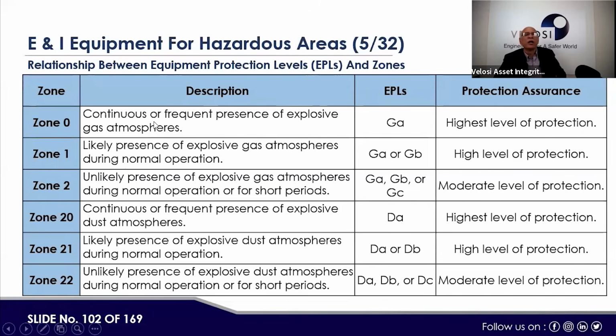Here in zone 0 we need Ga, in zone 1 we need Ga or Gb, and in zone 2 we need Ga, Gb, or Gc. Here the question is, Ga can be installed in the other 2 zones, but Gc cannot be installed in a Ga area. The levels are the highest level of protection, high level of protection, and moderate level of protection. The same is for dust: Da, Da or Db, Da, Db or Dc. A higher EPL can be installed in the lower area, but not otherwise.